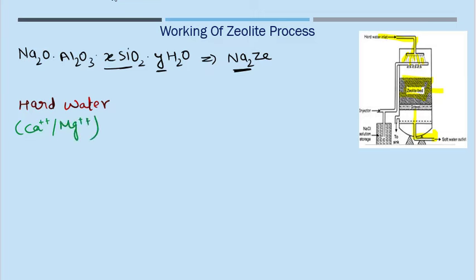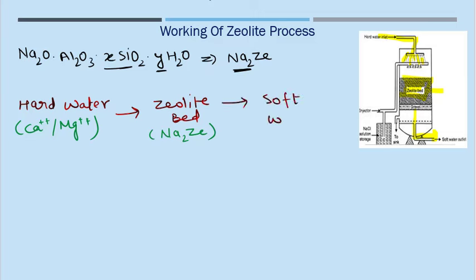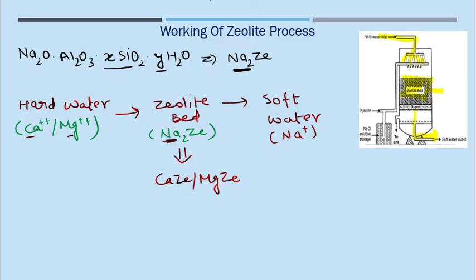Hard water does not give lather formation with soap. So when the water passes through a zeolite bed, which we represent as Na2Ze, the water comes out in the form of soft water — soft water means there is no hardness. The sodium ion is exchanged with calcium or magnesium ion, so the sodium zeolite is converted into calcium or magnesium zeolite, and the water will no longer be softened. We call this exhausted.